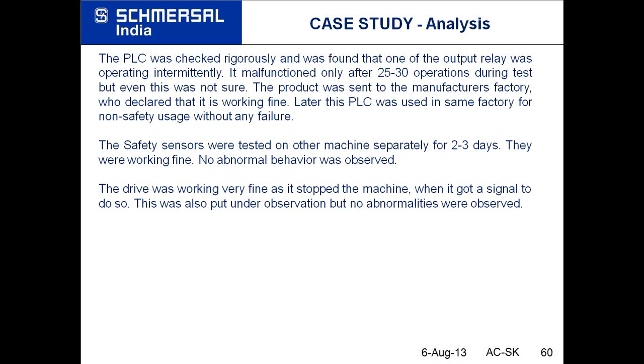Okay, the safety sensors were also tested on other machines and separately in the test circuit also for 2-3 days, and they worked very fine. There was no abnormal behavior observed. Then they also tested the drive system, but the drive was working very fine because it always stopped when it got a signal to stop the machine. And at that point of time when the accident took place, it didn't get a signal to stop.